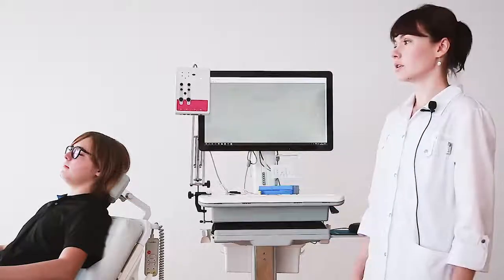Let's start with the otoacoustic emission tests. Actually, Neuro-Audio allows us to perform different types of otoacoustic emission tests, including spontaneous otoacoustic emission, transient evoked otoacoustic emission, and distortion product otoacoustic emission tests. All of them allow us to evaluate the state of the inner ear, in particular, the inner hair cells of the cochlea. In clinics, we often use only transient evoked and distortion product otoacoustic emission tests.